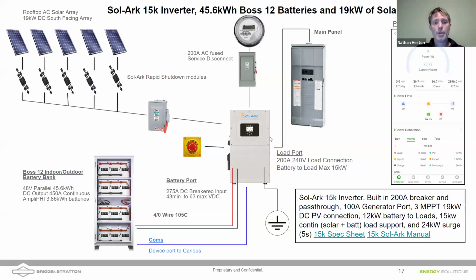Additionally, with battery backup, you have the ability to bring up to 275 amps of DC continuously from the battery bank in. It can surge to 25 kilowatts, I believe 24 kilowatts of surge for 5 seconds.